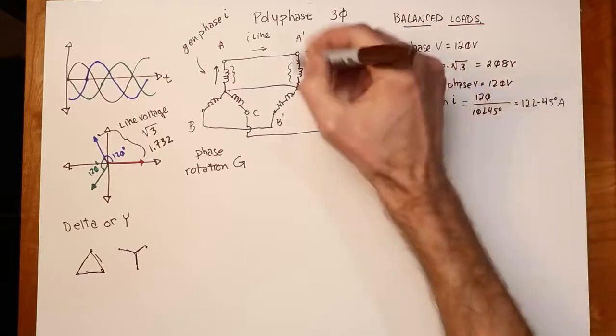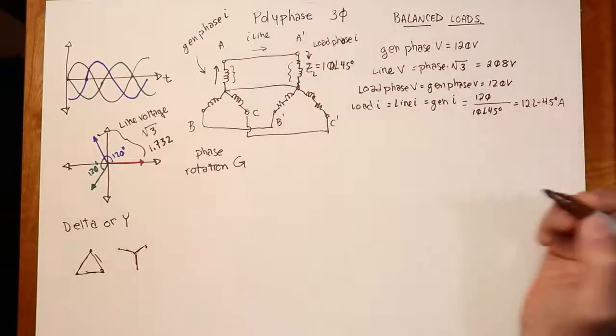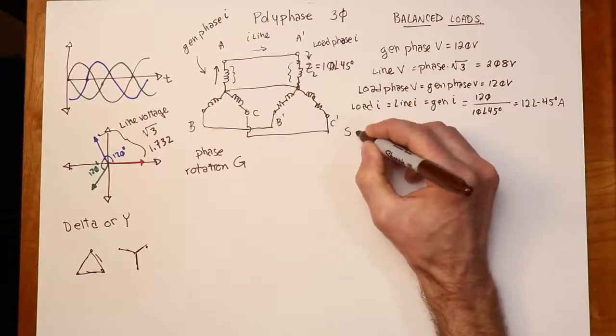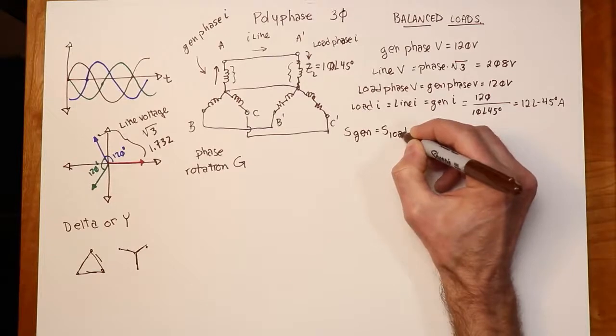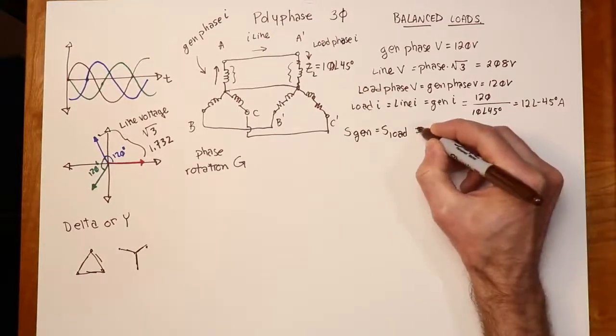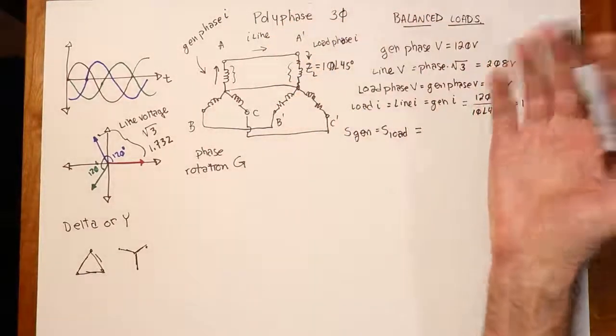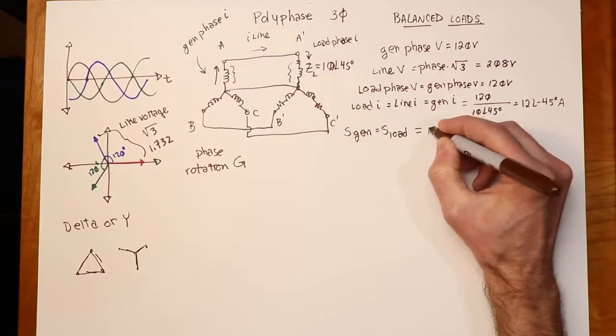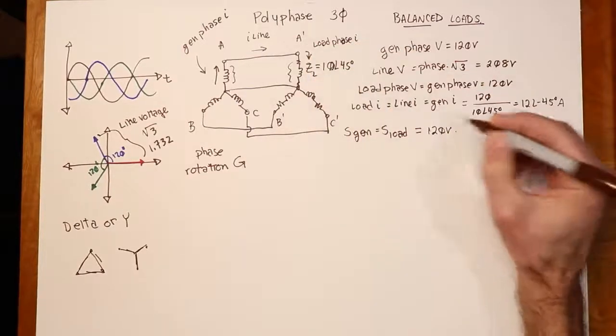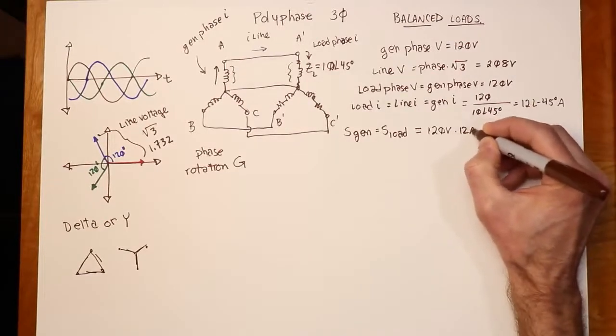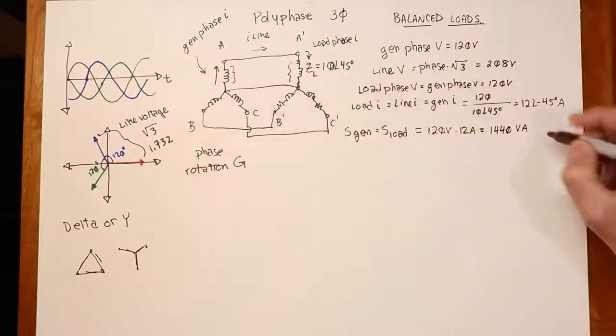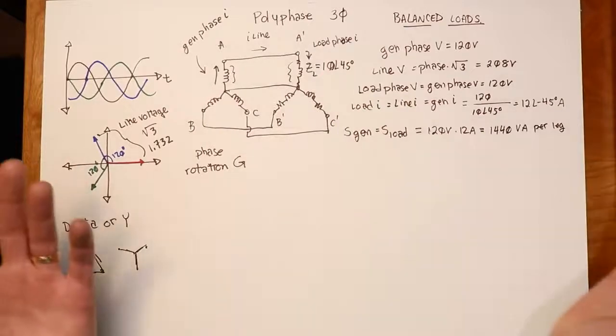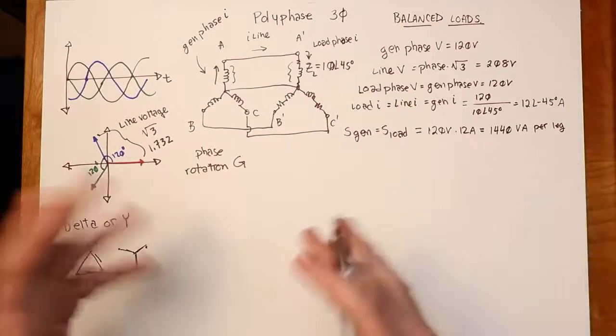From the current we can figure out the apparent power. It's always worth remembering that the apparent power from the generator equals the apparent power in the load. Apparent power — not true power — is the applied voltage times the current: 120 volts multiplied by 12 amps gives 1440 volt-amps. That's per leg, so the total apparent power in the system is three times that.